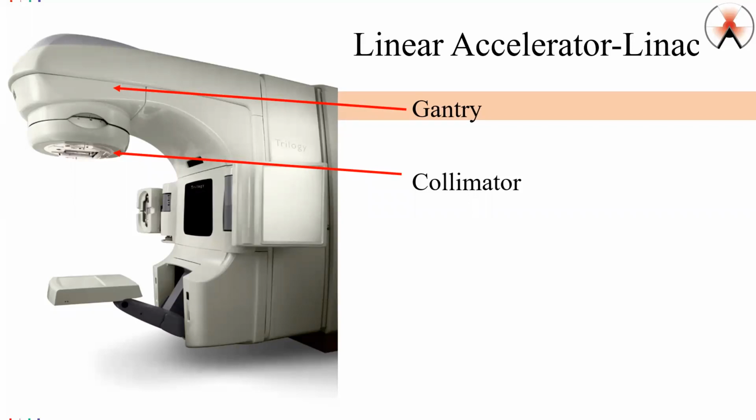Now, the other thing to know about these linear accelerators, let me just get my laser pointer here. One thing that's missing in this picture is the treatment couch. The treatment couch will be extended right here. The photon beam will be exiting from the equipment through this window. This is an opening. These are the collimators, and there are metallic leaves that are automatically controlled by the software and open to the shape of the treatment volume that is going to be irradiated within the patient.